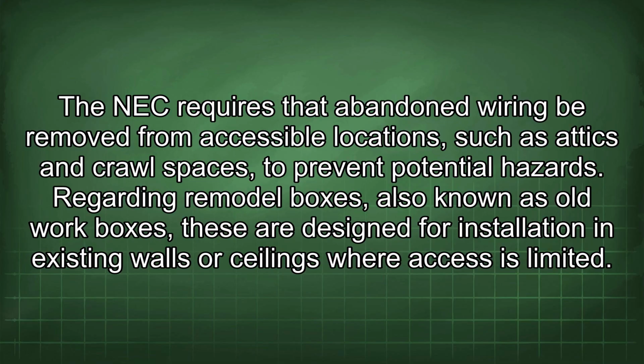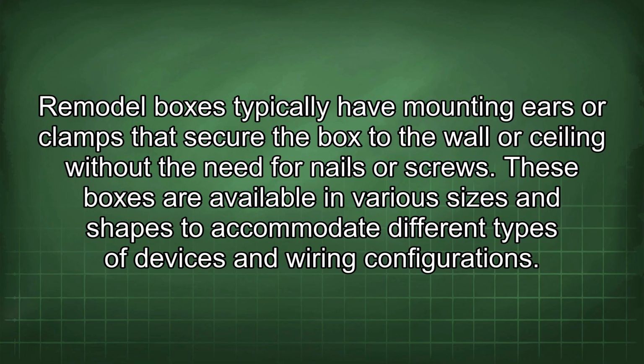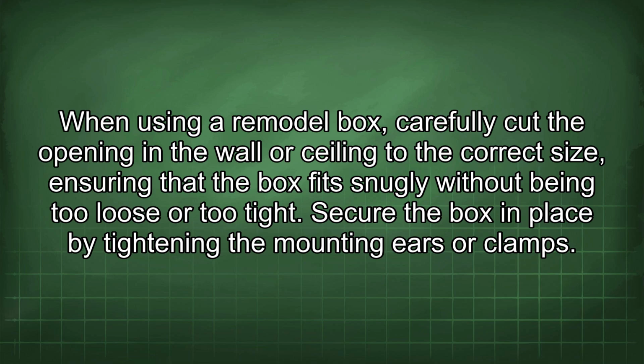Regarding remodel boxes, also known as old work boxes, these are designed for installation in existing walls or ceilings where access is limited. Remodel boxes typically have mounting ears or clamps that secure the box to the wall or ceiling without the need for nails or screws. These boxes are available in various sizes and shapes to accommodate different types of devices and wiring configurations. When using a remodel box, carefully cut the opening in the wall or ceiling to the correct size, ensuring that the box fits snugly without being too loose or too tight. Secure the box in place by tightening the mounting ears or clamps.